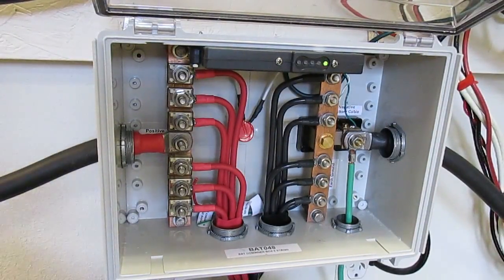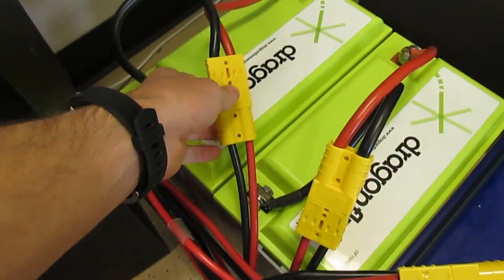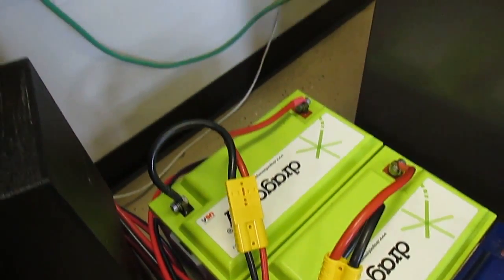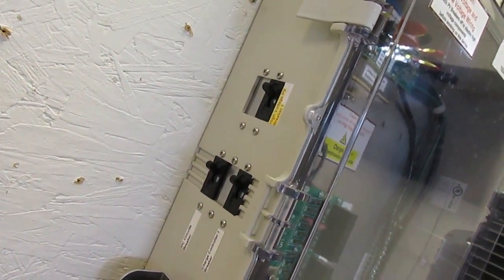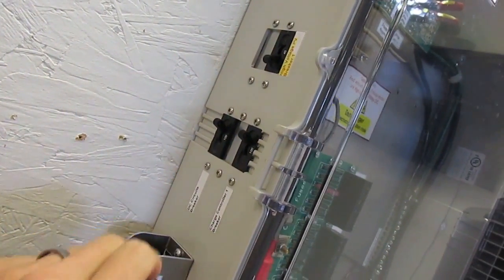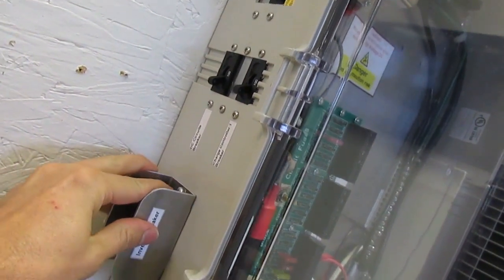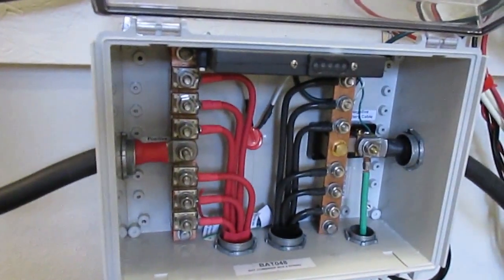If you need to change a fuse on the battery 048 combiner box, the first thing you need to do is disconnect the Anderson connectors on all of the batteries and then turn off your PV breaker if you have this box, or pull out the PV disconnect if you have one of the older boxes. All these other breakers you can go ahead and turn off just to be safe. Then you would unplug all your batteries.